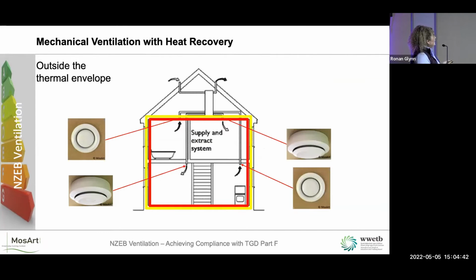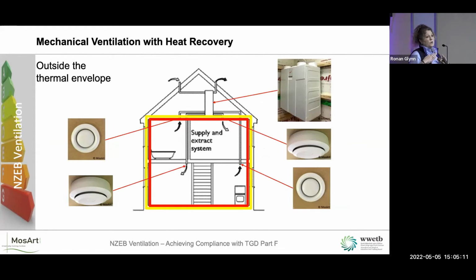You can, like I said, put your MVHR unit up in your attic. But if you're insulated on ceiling level there, you've got a lot of problems. You're paying a lot of money for a heat recovery system to hang on to that heat, to conserve all of that energy. And you might as well send it around the garden, insulate it, and send it back in again to the house. So once you take it outside your thermal envelope, it's outside it. So the only way it would really work in the attic is if you have your insulation on the slope of the attic. Okay, then there's plenty of usable space up there.